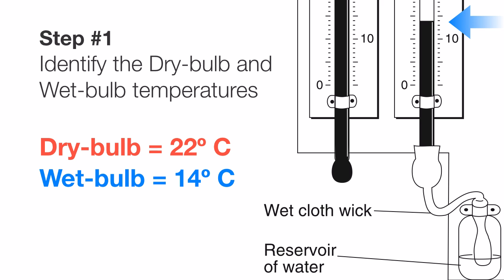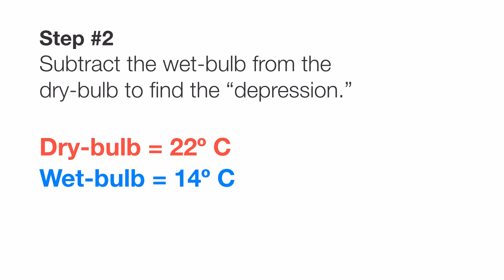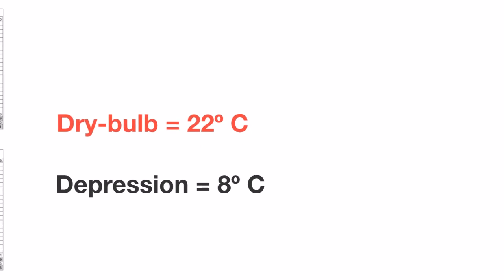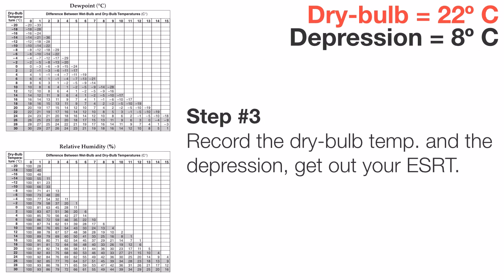So now that we have our dry bulb and wet bulb recorded, we have to go to step two, which is subtracting them to find what we call the depression. In this case, 22 minus 14 equals 8 degrees Celsius. Now the next step will be to go to our chart. We have to keep in mind we're going to record what our dry bulb is and what our depression is. Those are the two important numbers.